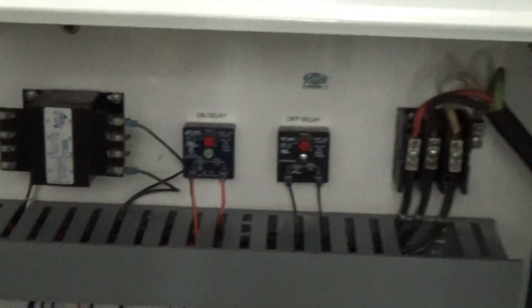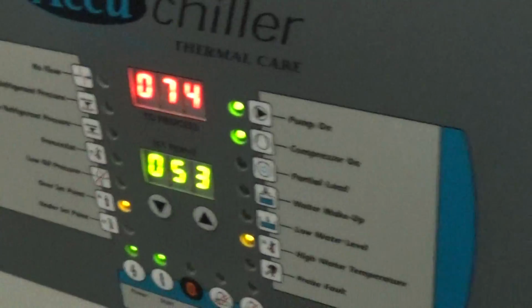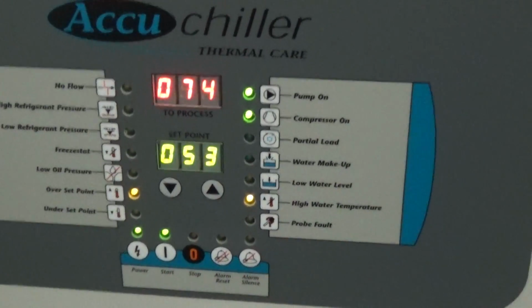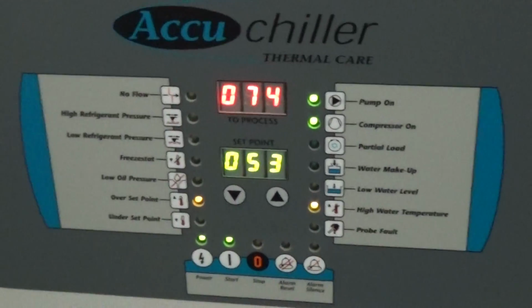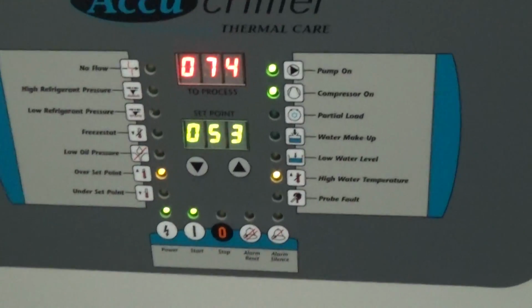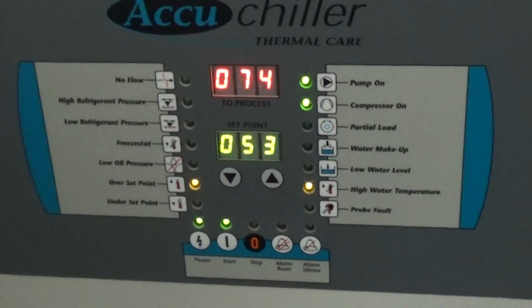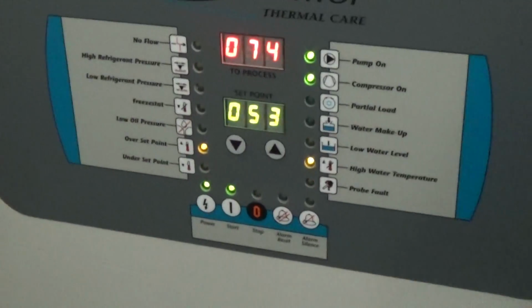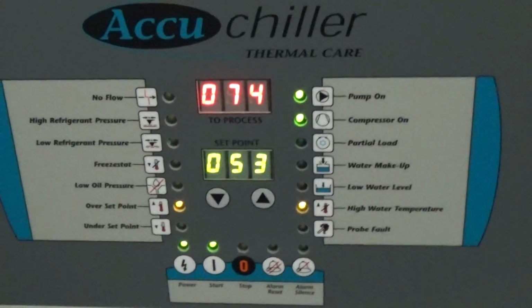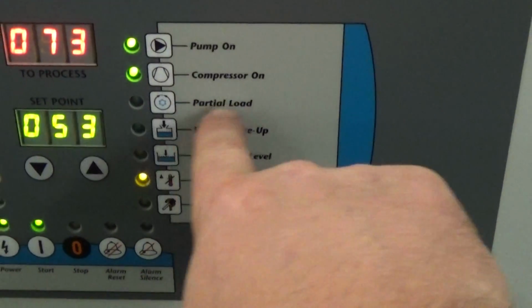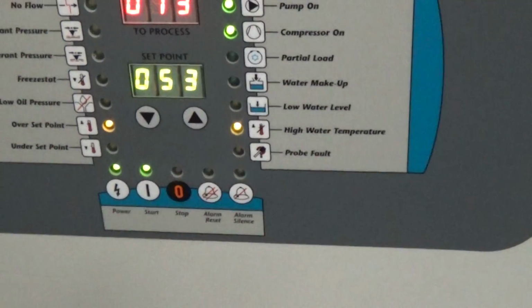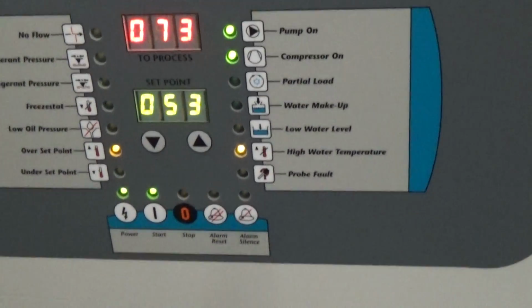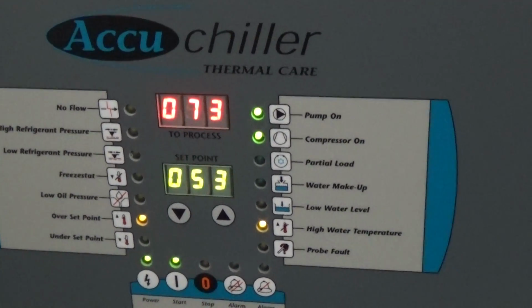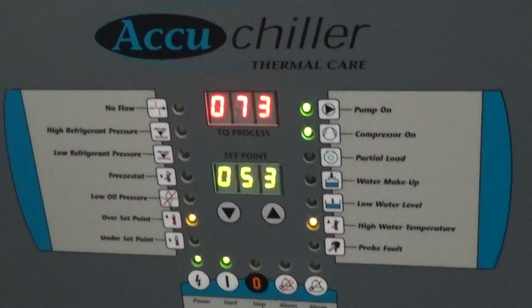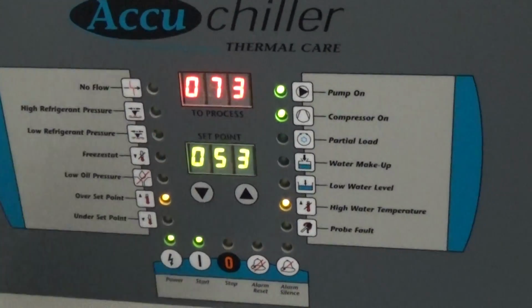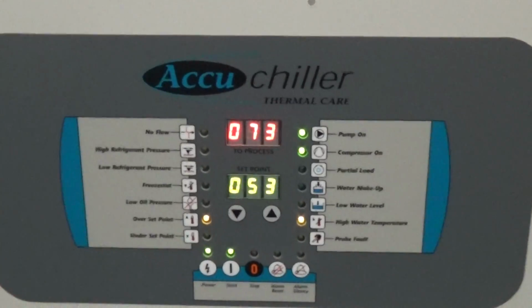So the logic is, while you're running, if you meet set point within a certain period of time, say 2, 3, or 4 minutes running off one compressor, that's all you want to do. If after an adjustable amount of time you're not meeting set point, then the second compressor will kick on. Conversely, when we get closer to the set point range, in this case 53, the hot gas bypass, which is indicated by partial load, will come on, and we actually have an off delay built into the other compressor. Between those two things, we can explain it in more detail over the phone to the customer. You have some adjustability to fine-tune a very simple staging of this unit, which again is above and beyond what the factory did as standard.